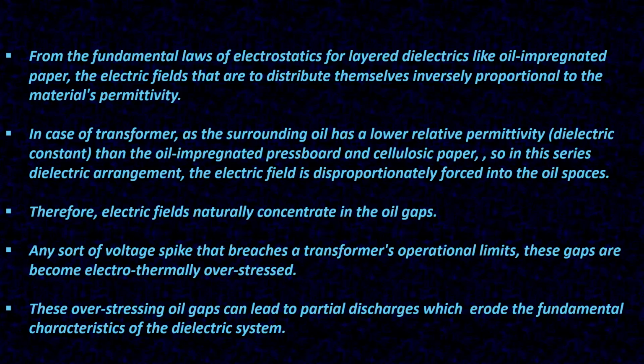Therefore, electric fields naturally concentrate in the oil gaps. With any sort of voltage spike that breaches a transformer's operational limits, these oil gaps become electrothermally overstressed. These overstressed oil gaps can lead to partial discharges, which erode the fundamental characteristics of the dielectric system.